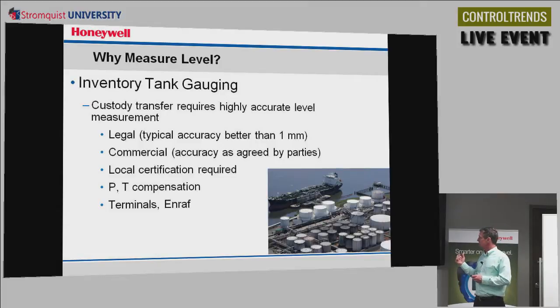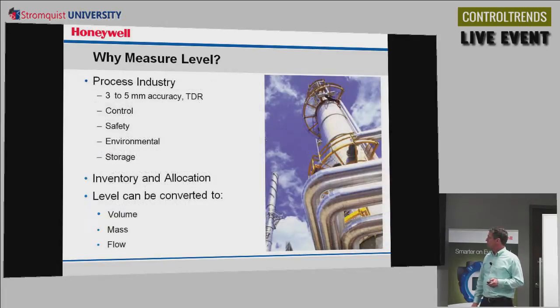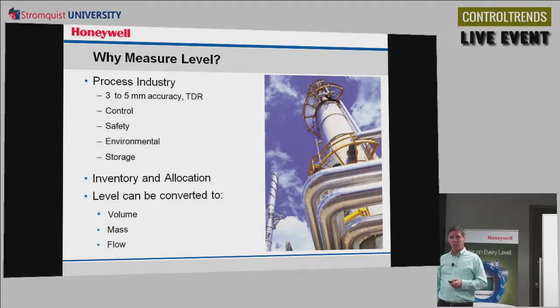They're higher performance. These work at terminals, and it's often our sister company, Enraf, who provides these inventory tank gauging. So that's really not going to be our concern with the process gauge. That's a different kind of level measurement. So for what we've been talking about, it's mainly about the process industry. And for the process industry, 3 to 5 millimeter accuracy is good. It may be for control purposes that they measure level, could be for safety, environmental, and for storage as well.